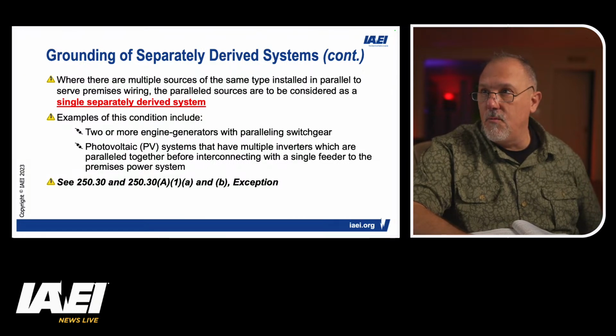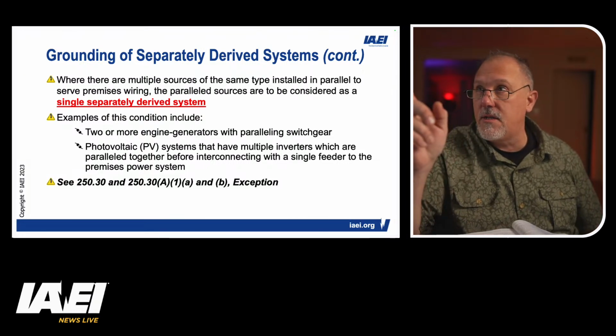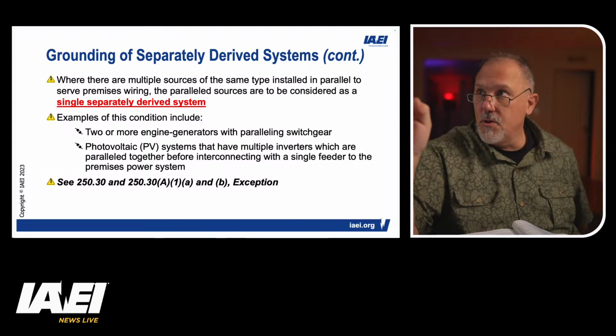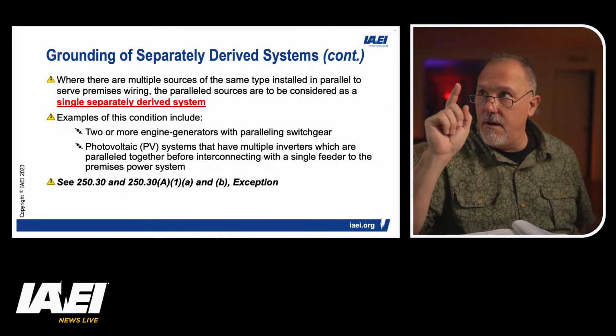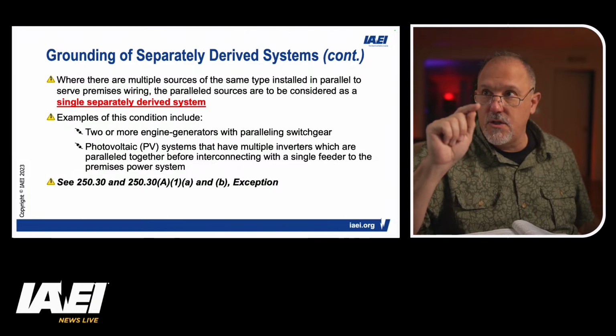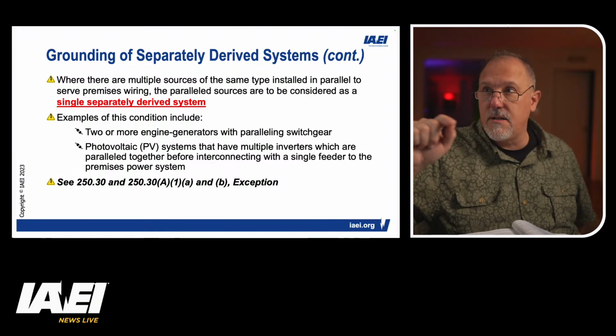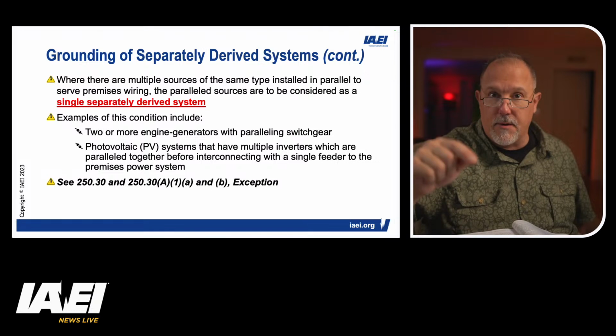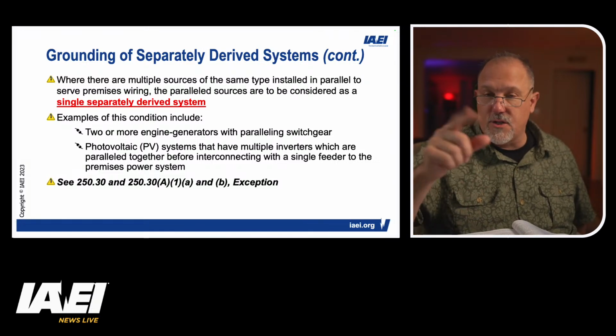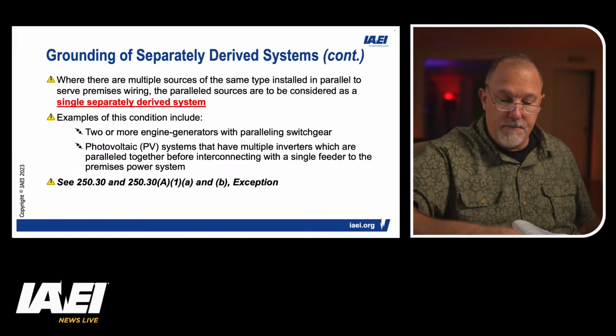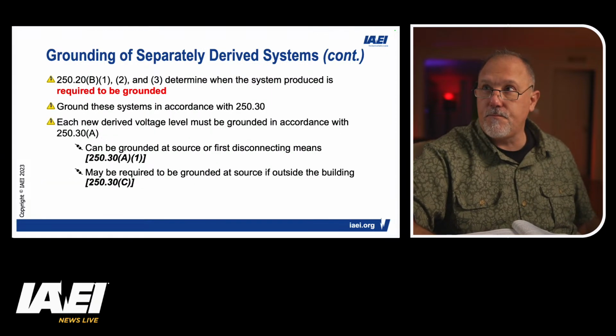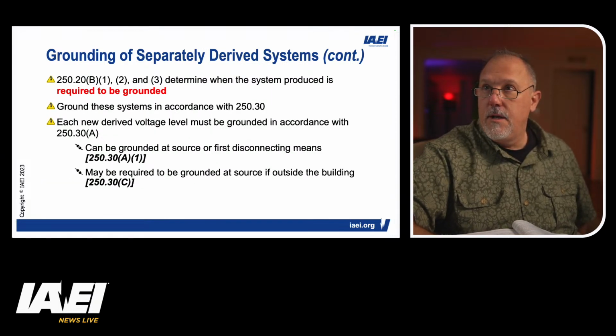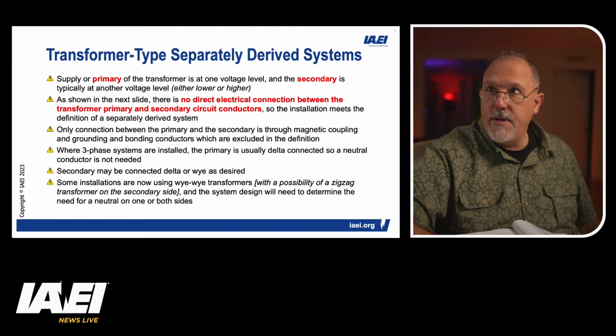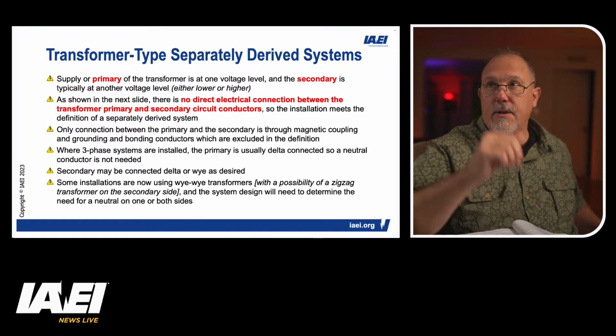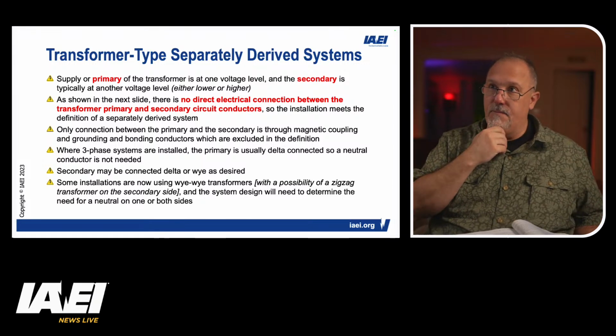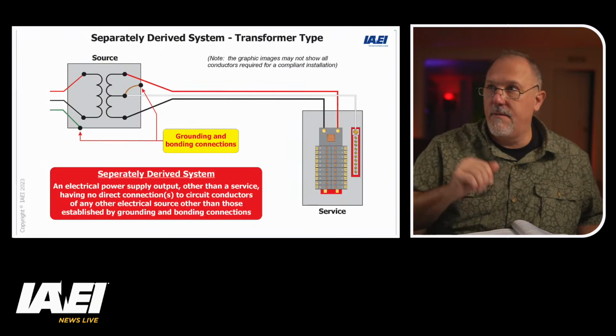Examples of the condition: 2 or more engine generators with paralleling switchgear. This is multiple sources of the same type. So this is your PV systems, your 2 or more engine generators with paralleling switchgear, etc. And we just read 250.30(A)(1), and you have A and B of that. All right, so we know we have to decide when it's going to be grounded. Let's do this. I love pictures.